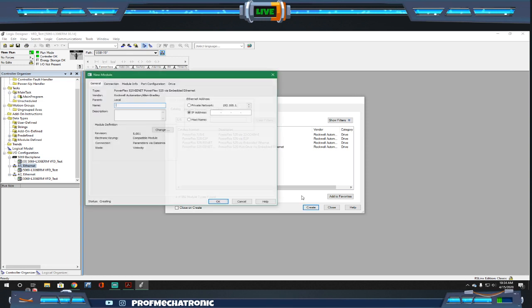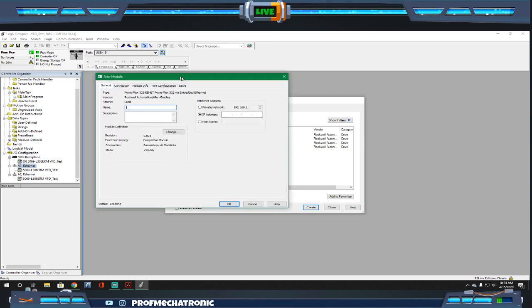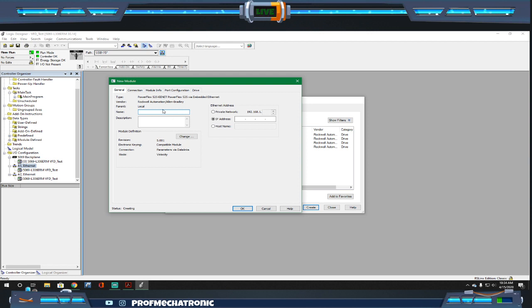So this is going to start to look a little bit familiar, hopefully, as far as creating a new module goes. We have the new module show up. At this point, we have to give it a name, look at the module definitions, pick the Ethernet addressing. All of that stuff needs to happen right from in here. So in this particular case, I'm just going to call this PF525. We'll keep that nice and simple. We know that the IP address of this drive is 192.168.1, and we are going to put a 5 in there because that's what we manually set up on that drive on the right-hand side.